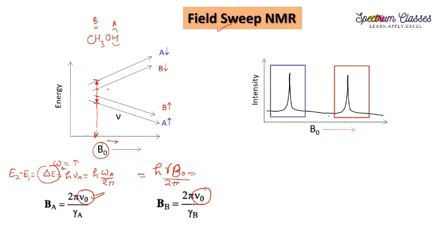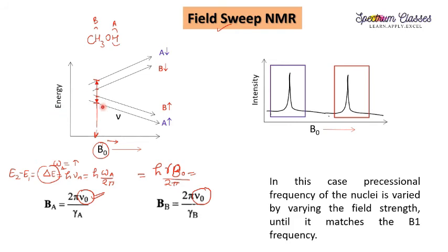As shown in the animation, as the energy gap increases, at a certain B0 value the energy difference equals the constant frequency value and resonance occurs. This specific field strength is required for nucleus B, and a different field strength is required for nucleus A. This explains how, at constant RF oscillator frequency and varying B0, the two different nuclei achieve resonance in the field sweep NMR spectrometer.